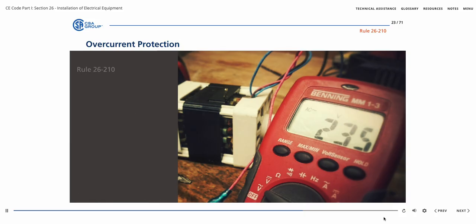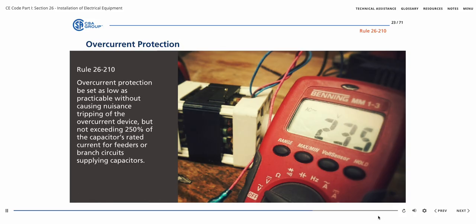Rule 26-210 requires that the overcurrent protection be set as low as practicable without causing nuisance tripping of the overcurrent device, but not to exceed 250% of the capacitor's rated current for feeders or branch circuits supplying capacitors.